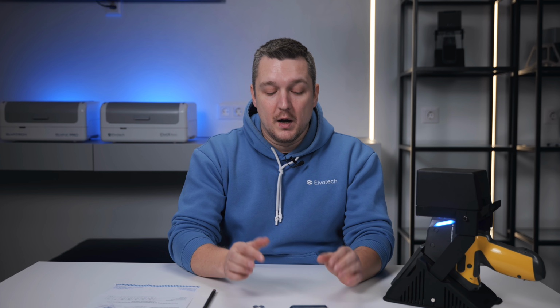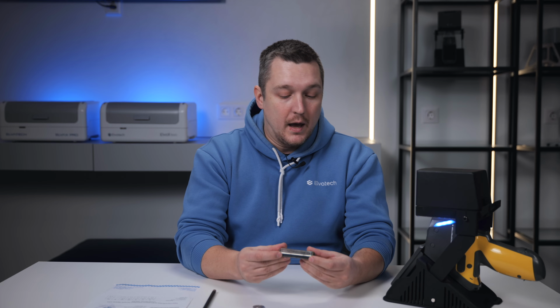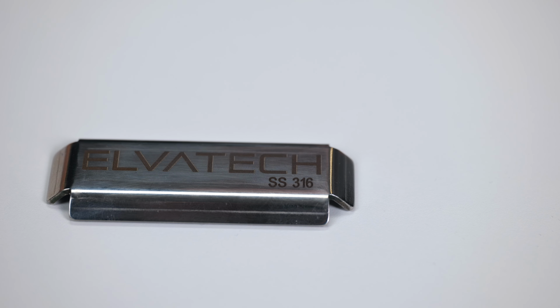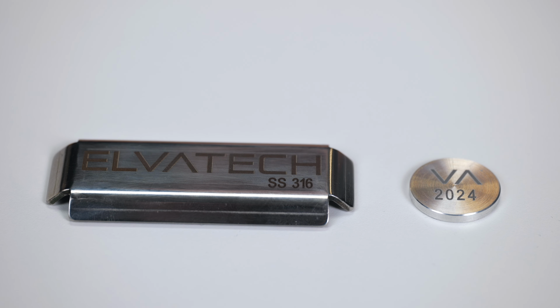You don't need to perform energy calibration all the time, just in case. Instead, you should periodically check the instrument using our reference samples of 316 stainless steel for heavy elements and 2024 aluminum alloy for light elements. The procedure is very simple. From time to time, for example after transportation or once every 6 months, measure the 316 stainless steel reference sample that comes with the analyzer and 2024 aluminum alloy if you have the model with light elements.